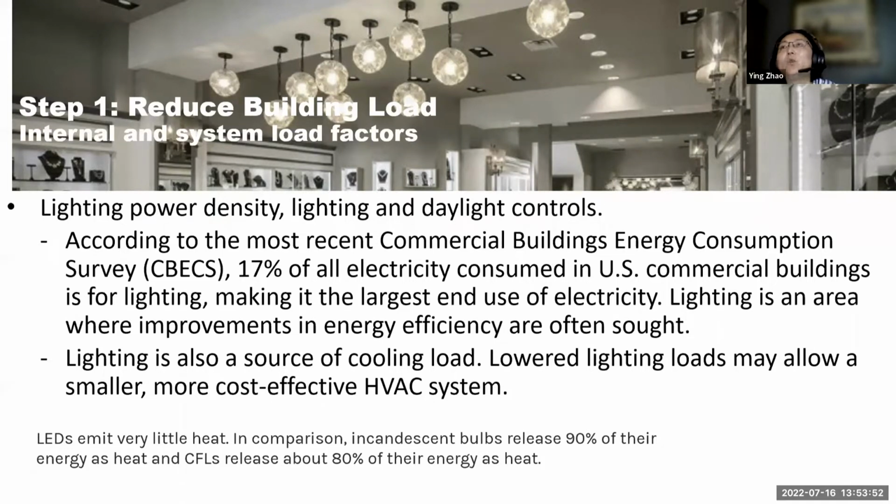LED is much more expensive than fluorescent light bulbs, but it will last very long. The typical life of an LED is at least 20,000 hours. It can reach 50,000 hours, and they won't break. But the fluorescent ones can break very easily, and the life of the lamp is very bad, especially the compact fluorescent.